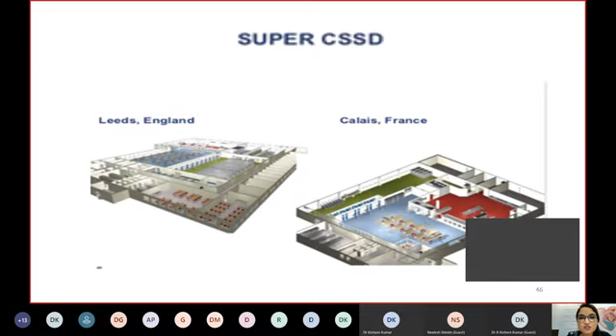Then there is another important thing that we should know: there are three important quality controls that we monitor in CSSD. The first is physical control, which is displayed by temperature, pressure, and gas concentration. Then we have chemical indicators, the strips which are put on the packs. When there is a color change, it indicates that it has been successful. We have 6 classes of chemical indicators, of which the Bowie-Dick, the class 2 one, is not a sterility test. It checks for air pockets or air leaks. The remaining ones check for sterility.